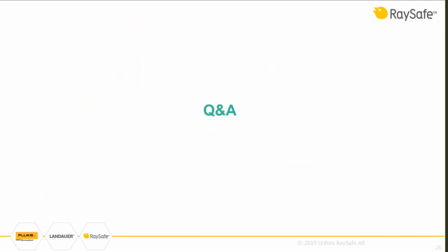And Göran, have we received anything on the question? Feel free to continue to ask as well, of course. Yes, we do have some questions, and I will take them in the order they came in. The first one is whether we can use the 451P to measure X-ray leakage. Generally, yes. X-ray leakage from a diagnostic X-ray machine, for instance, with no problem.